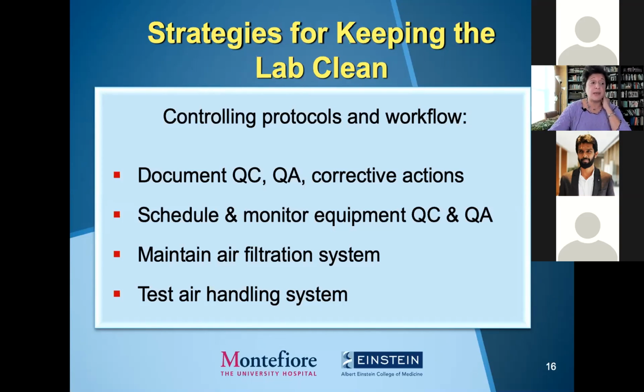In addition, incubator seals can break down from overheating. Dust buildup can occur in equipment not routinely in use, and degradation of tubing can introduce contaminants into the gas supply. Regularly scheduling equipment QA for laminar flow hoods, incubators, and microscopes ensures proper operation and cleanliness. All equipment should undergo an electrical safety check annually. Service the air filtration system at least annually, and if possible, do a testing and balancing of the entire HVAC system every two years.